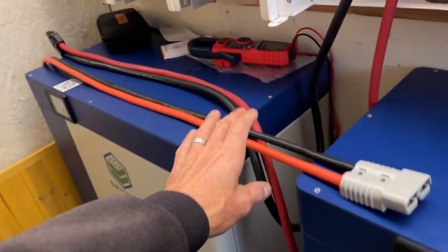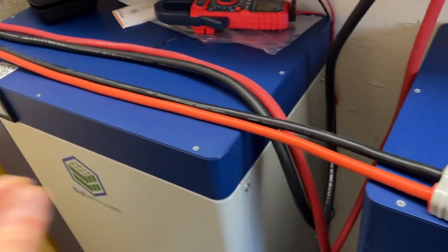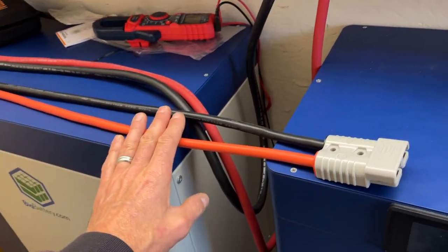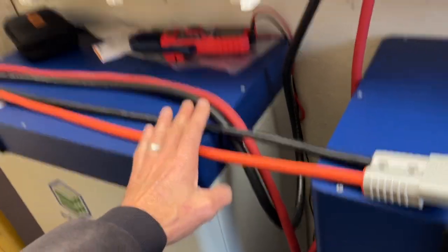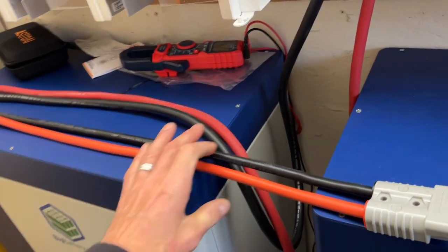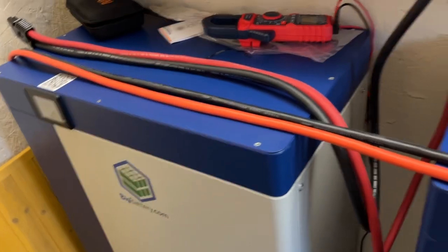But this - yes you can do it - but you literally have to connect directly to a bus bar, keep it free air. You cannot put it in burial, you can't put it in cable, you can't put it in conduit, you can't put it in raceway, you can't do anything else with it. You cannot guard this from physical damage potential.